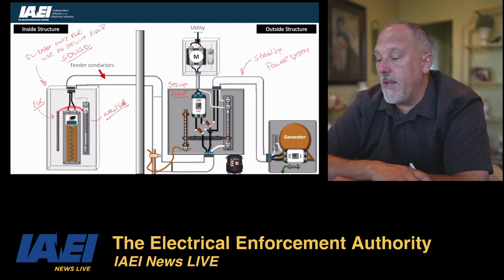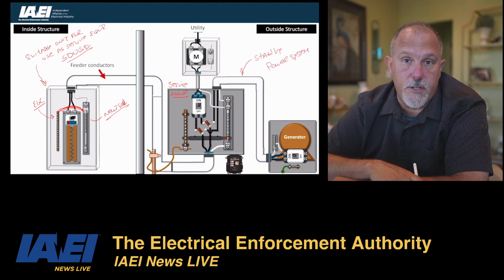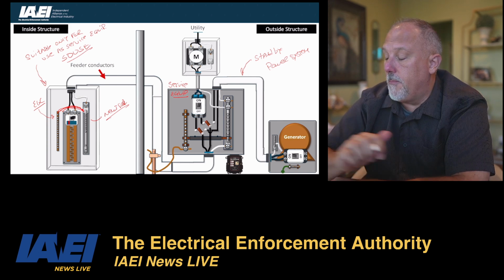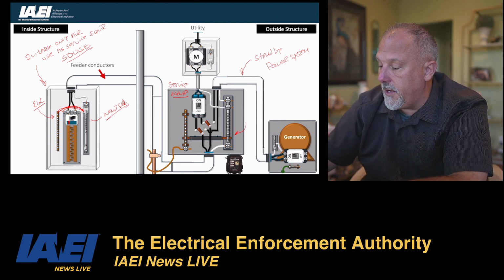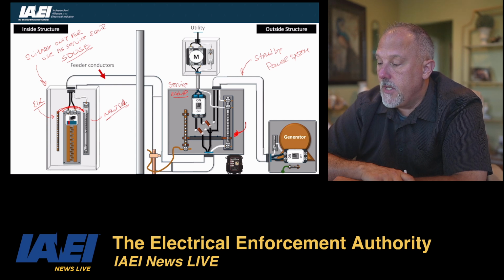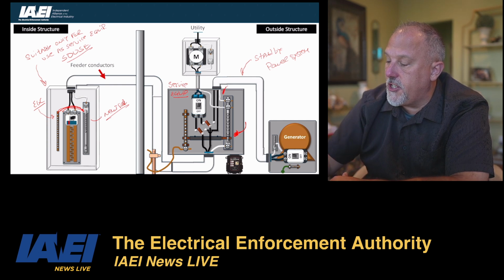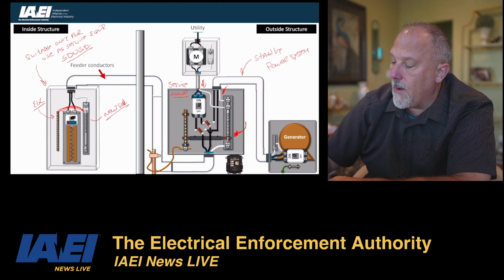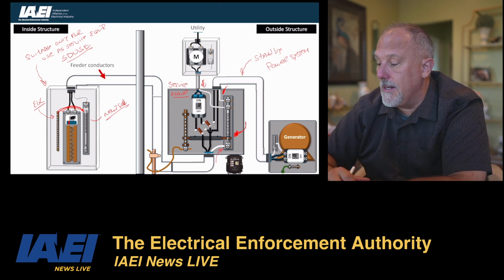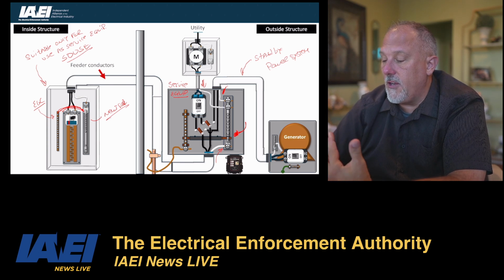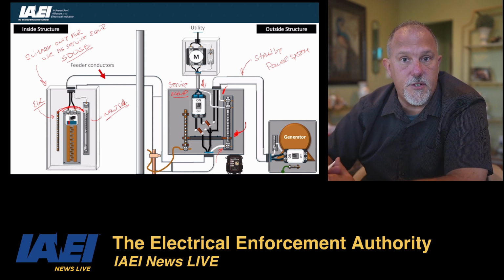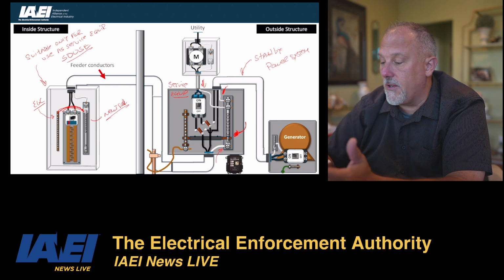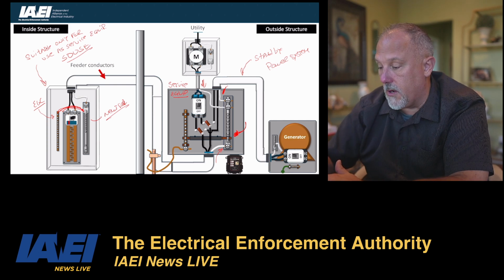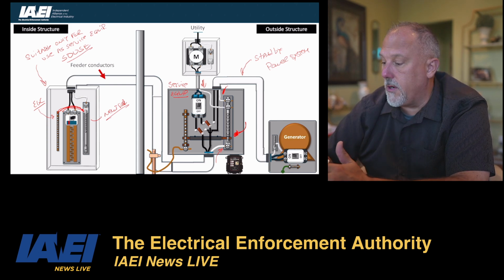But when you install it, you're going to have to bring the grounding electrode conductor, which goes to the grounding electrode system, to that equipment. The bonding will automatically be done, and I'm showing that bonding right there. That bonding would have to be done there. You would land your grounded conductor from the generator on that bar. You would land the grounded conductor from the utility on that bar. You would land the grounded conductor that goes to the load on that bar. And you would land the grounding electrode conductor. If the bonding strap is there, then you could land it on either the equipment grounding conductor bar or the neutral bar. Or you land it directly on the neutral bar. So you would have to have enough lugs.